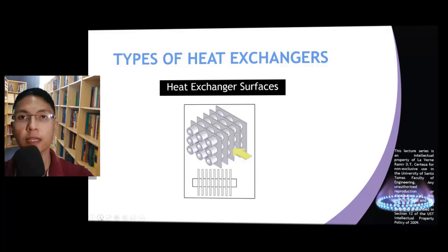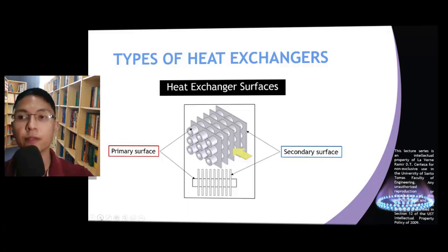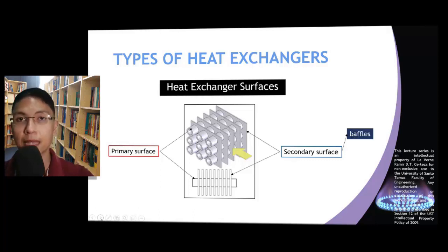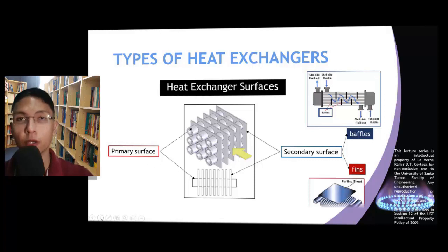The surfaces found in a heat exchanger can be classified into two based on their intended purpose. A primary surface serves to separate the hot fluid and the cold fluid, thereby preventing the two fluids from mixing. A secondary surface can have two functions: it can either direct fluid flow or increase the heat transfer surface area. An example of a secondary surface that directs fluid flow is baffles, commonly found in shell and tube heat exchangers. An example that increases surface area is fins.